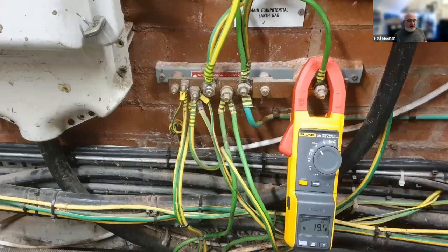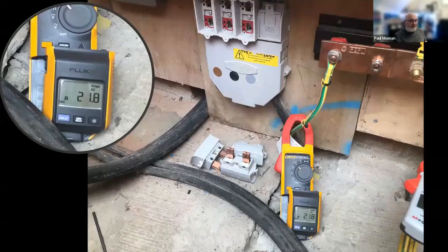Here's a picture that I took. There's 20 amps on an earthing conductor. So that's the fixed electrical installation to the power supply. Don't really want 20 amps on an earthing system, considering that in England, I was taught that it's a benign conductor with 0 volts. Generally, there are millivolts behind this, but we'll get into that phenomenon in a second.